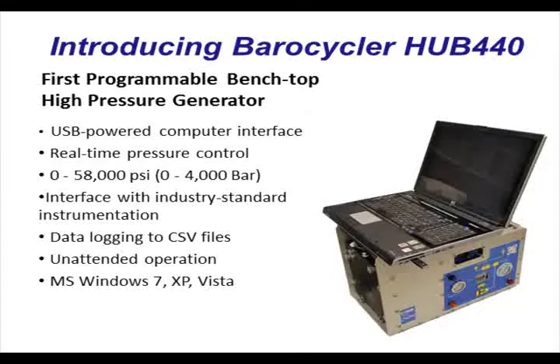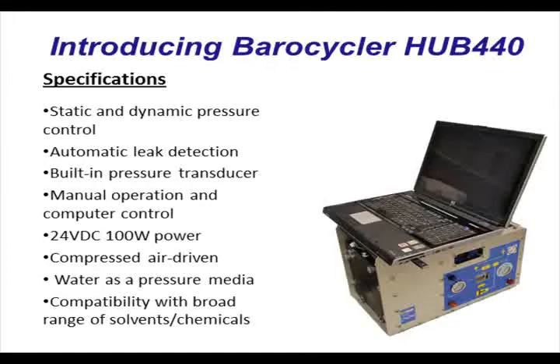This instrument is a plug-and-play pressure generator bundled with a USB computer interface and powerful software control suite, which enables any laboratory to perform high-pressure research right out of the box. At the heart of the HUB440 is an air-driven intensifier that uses compressed air to generate hydrostatic pressure up to 60,000 pounds per square inch, or up to 4,000 atmospheres.